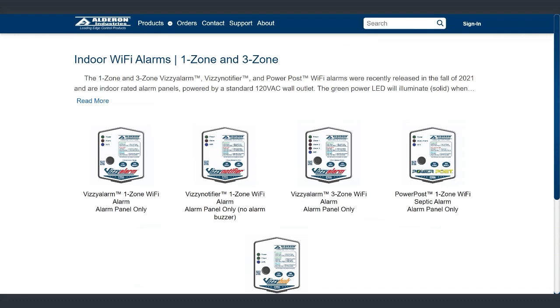I'll just leave this cable up here, but let's pull this apart. And you can see this is a 3-zone Wi-Fi that has a battery backup included and temperature sensors. So you can set those different sensors up and program, if it goes below 48 degrees or 45 degrees, you can get a low temperature alarm, so you can get an early warning notification. Hey, the furnace is off, come and fix the situation before your pipes freeze. Or maybe if it gets too warm, you get a notification for that. Maybe if it's in a cooler or something, if the temperature gets too warm, you get a notification.